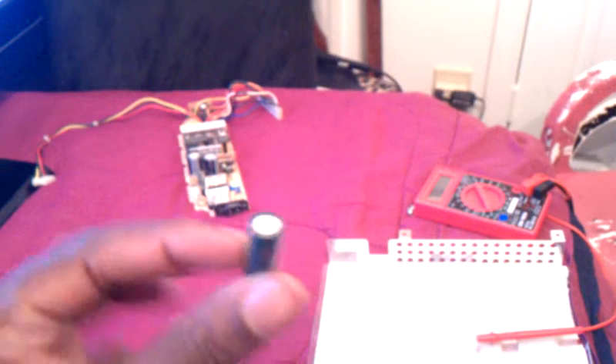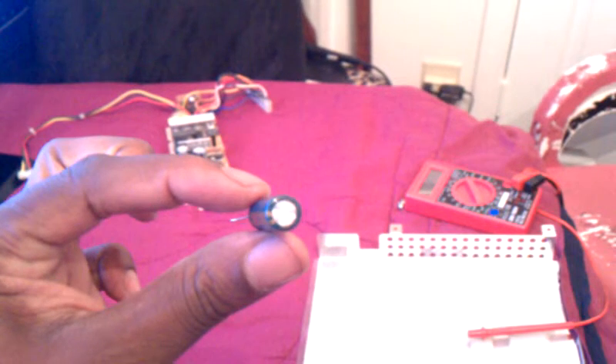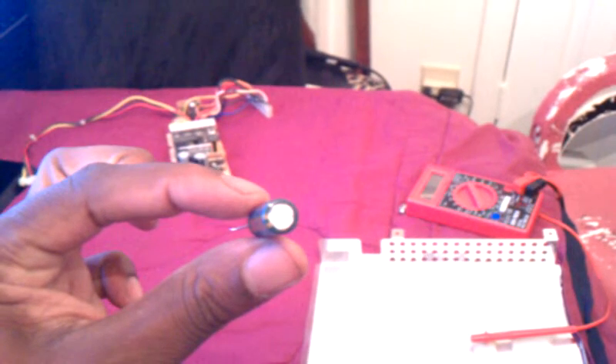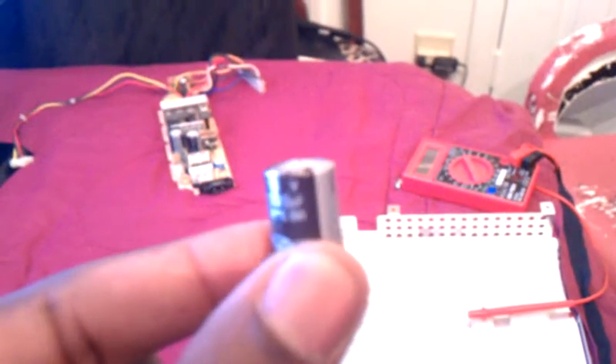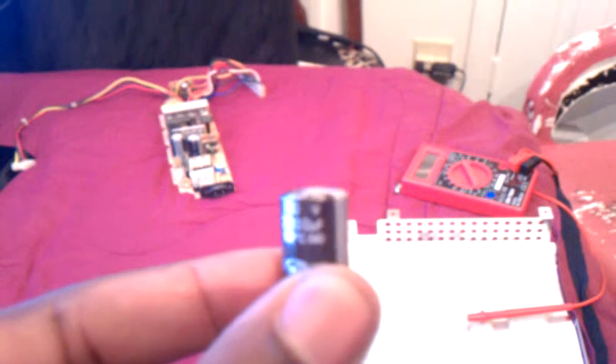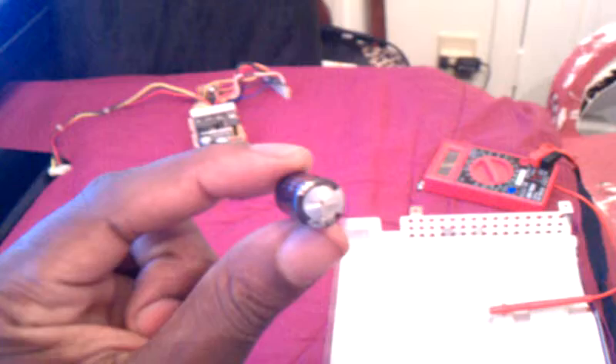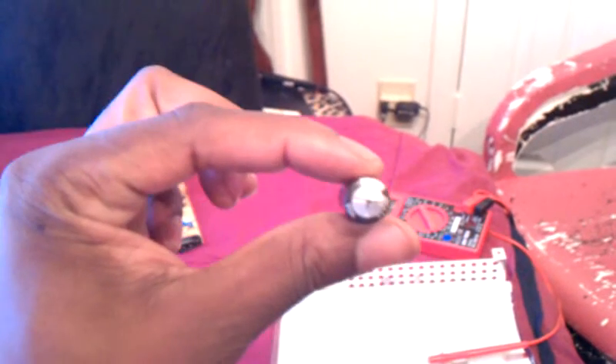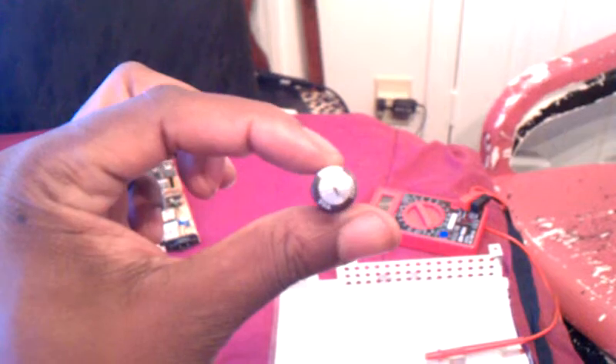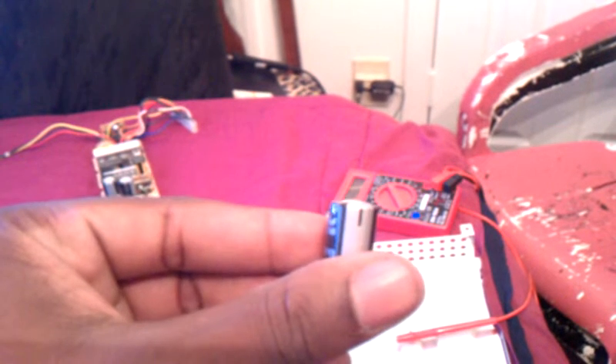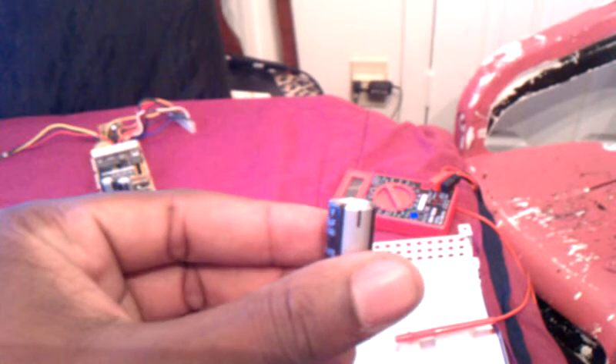What you can tell is, I'll show you from one of these good ones over here. You can look at the top of it and the top looks flat and it doesn't have any of the stuff on the inside, none of that on top of it. But as you can see on this one, this one is bulged out on top, see a little curve at the top? And if I can find one, that one, see how it has the black stuff right there in the middle? Whatever's on the inside is squirting out from the surge. See, that's bulged on top.